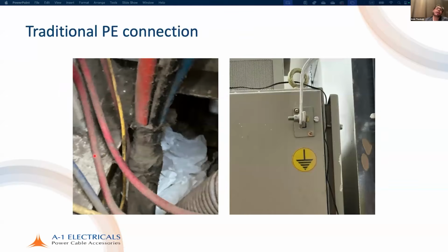But in India, oftentimes we see that this is not being done. Very common arrangement is that we will bring in an armored cable from the bottom of the panel, and of course, in typical fashion, there will be garbage that is stuffed there. This will be taped over, the armor will be taped over, and the cable will be brought in. You can see there's absolutely no protection against ingress of dust or anything over here. And on the side, there is a GI strip that comes inside. Now, what are the problems with this? There are several problems, but I'm going to focus on the problems relevant to the requirements we saw now.